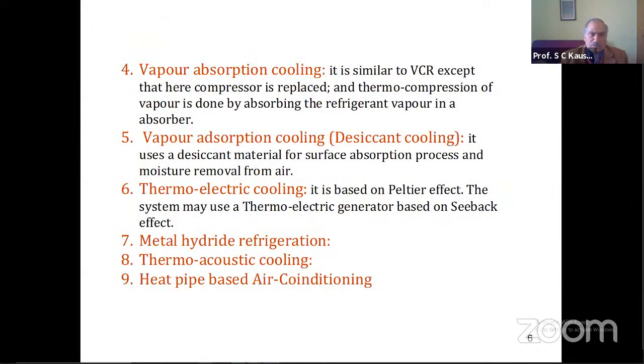The other option is the vapor absorption cooling system, which is similar to the vapor compression system, where the mechanical compressor is replaced by a thermocompressor, which is nothing but a combination of heat exchangers, generator and absorber. And in addition to a refrigerant, we also use an absorbent, a refrigerant-absorbent combination as a working fluid. Another option is vapor adsorption cooling, which is also useful for desiccant cooling options for controlling the humidity as well. It uses a desiccant material for surface adsorption process and moisture removal from the air.